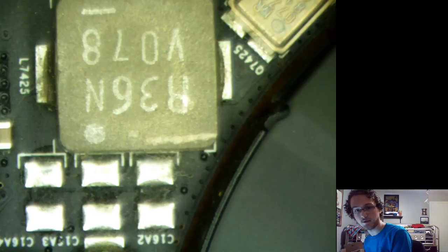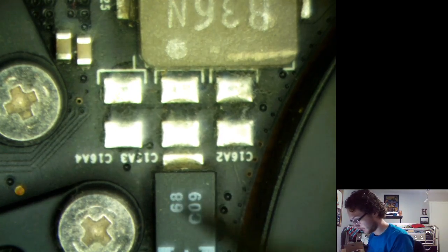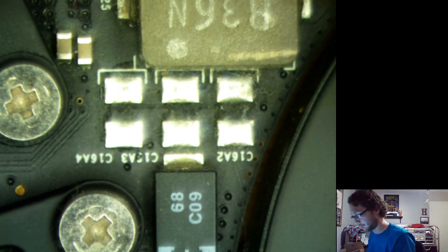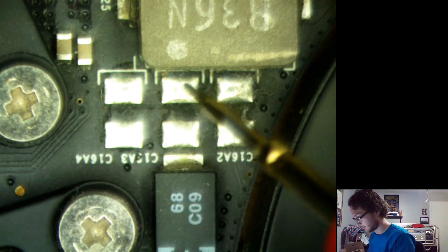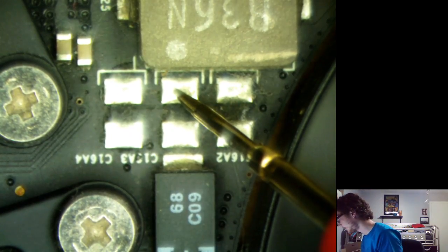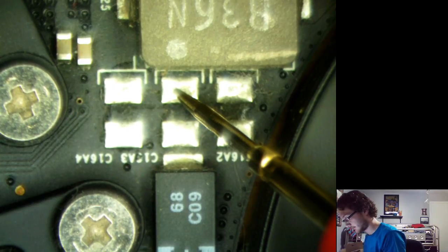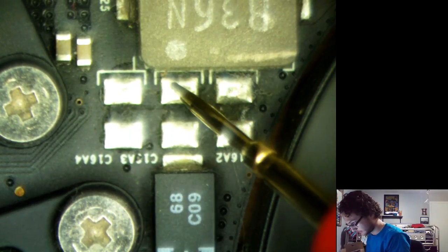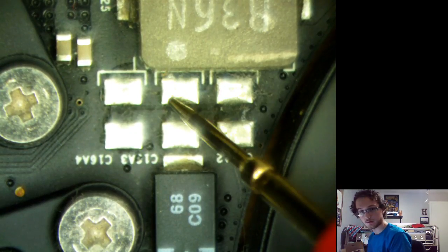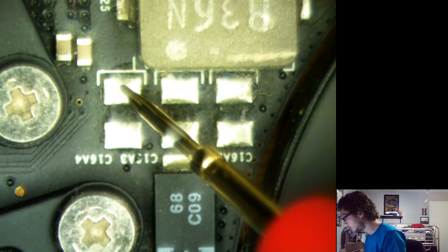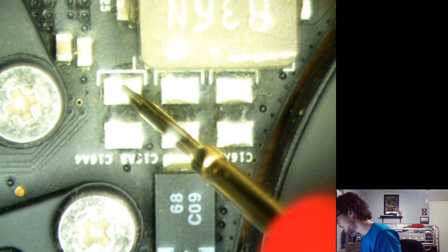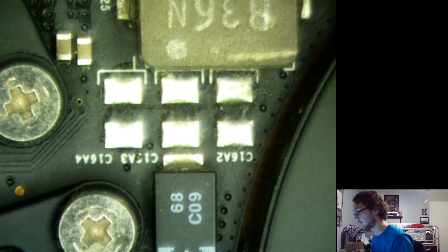So let's go ahead and switch back over to the microscope, and then we'll get that checked out. So that's going to be this little spot right here. So let's stick the multimeter on there and verify that it is indeed turning on. So we're going to put one probe on ground and one probe right there. And we appear to get 10 millivolts, which means that the computer is not turning on.